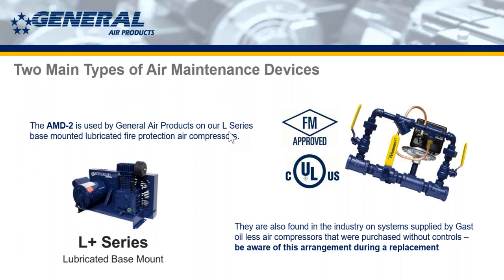Now you have two pressure switches essentially. So you have to make sure that only the pressure switch that's on the compressor in that situation is the one that's wired up. The air maintenance device, frankly, should probably be removed and replaced with just a small piece of pipe. The reason I bring this up is every once in a while, more often than I'd like to admit to the industry, we get a call from people who have both pressure switches wired up. And that causes chaos for the air compressor.